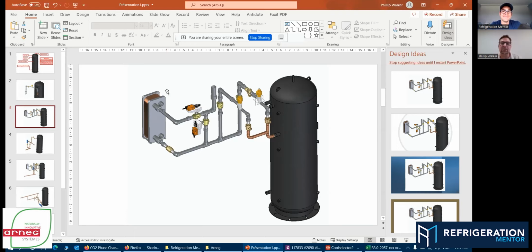And I'll say every degree you knock off is a significant impact to the system, a significant impact to the overall performance and stability of the system. Water or glycol is something we enjoy because it's very stable. It's a very stable fluid to work with. It's very predictable. And I love that when you look at a CO2 enthalpy diagram and you see when you start to drop that temperature of that gas coming down, it makes a world of difference in the amount of flash gas that's going into the tank. So it's super neat that you built this design.